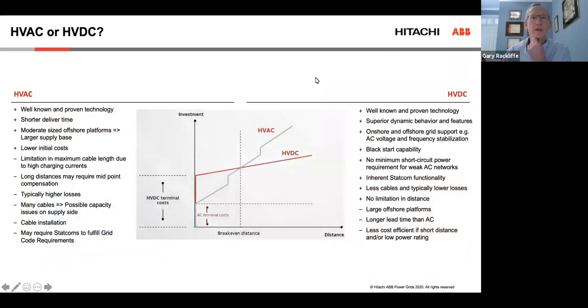So I know that Brandon and Jonathan talked a little bit about HVDC and high voltage AC. This shows the cost comparison, comparing the cost for HVDC, which is shown in red, and high voltage AC, which is shown in gray. The key component of cost with high voltage DC is that it has lower losses. The reason the losses are lower is a cable is a linear capacitor. And as you increase the length of the cable, you increase the capacitance.